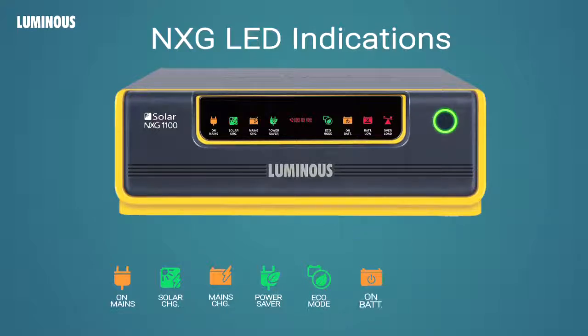On battery display indicates that the UPS is running on battery. Battery low display indicates that the battery is exhausted. Overload indicates that the system is under excessive load and load must be reduced. This is accompanied by beep alarms. And finally, if ever there is a problem in the system, the smart UPS indicates that itself — the service assistance display lights up to let you know that you must contact Luminous Service for help.